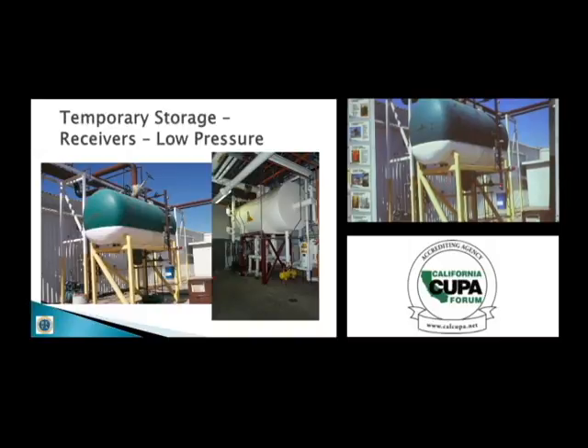But here's a great example of a way you don't want to operate. With ammonia, the pressure and the temperature of ammonia at 32 degrees is roughly 49 psig. So if we've got ice forming here, you could assume, hey, the pressure in this system is less than 49. You don't know how much less, but it is at least low, relatively speaking. I see relief valves, but I don't see carry-away piping. There's a lot here to final exam.